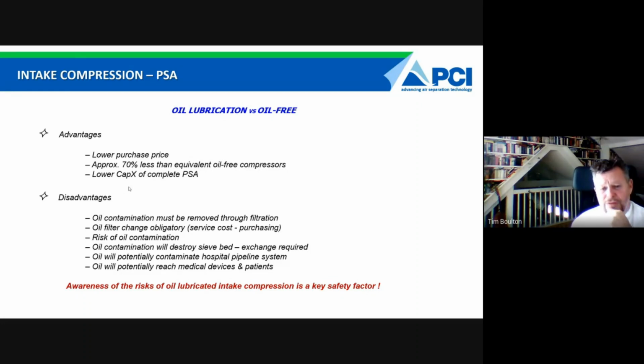You must remove the oil. So the oil contamination of the product must be removed through filtration. Therefore, your oil filter change is key. It's obligatory. You must keep changing the oil filters. If you do not, then you'll get oil into the system, and oil into zeolite, into an oxygen generation plant, will actually kill the zeolite. You cannot clean it. You must then either change the tank of zeolite or try and open the tank and remove the zeolite. It can go further than that.